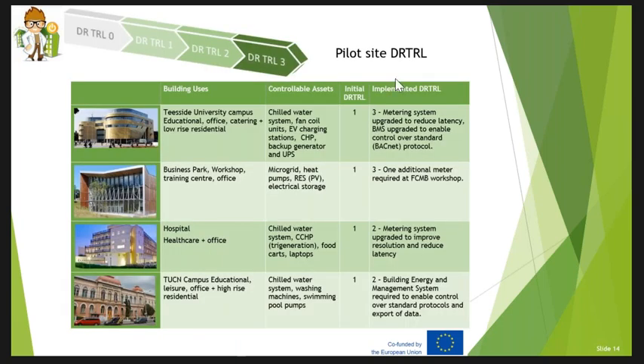So in terms of the pilot site demand response technology level, the initial TRL was 1, indicating that we could apply some manual controls, manual response to events, but we didn't have full automation. The implemented technology readiness level was 3. The main technical upgrades were that the metering system was upgraded to give us better real-time measurements. The building management system was upgraded to enable control over the BACnet protocol. Also, another point which is missing from this little slide was we designed and implemented the frequency sensor to give us fast response to low frequency events.